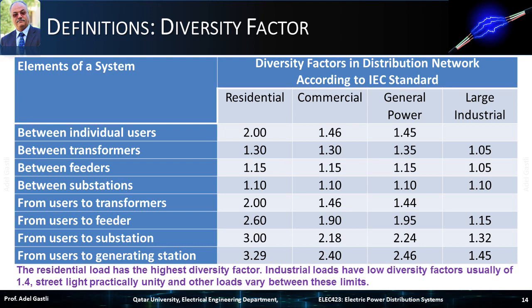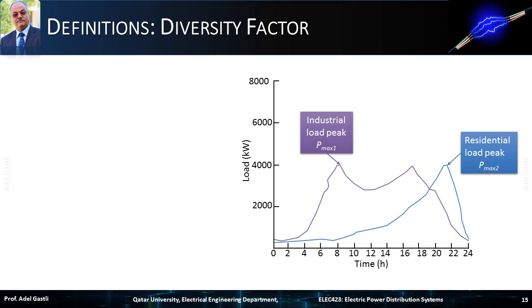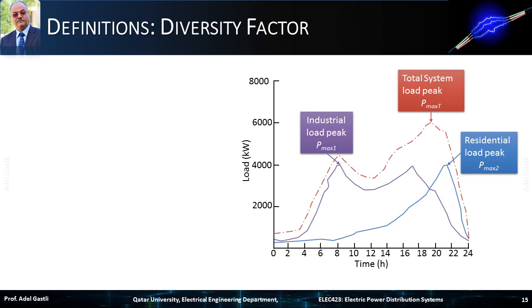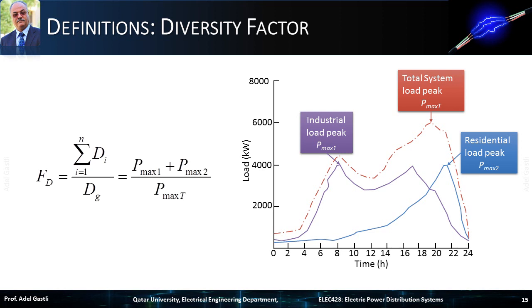Note that the more upstream you go, the higher the diversity factors. The residential load has the highest diversity factor. Industrial loads have low diversity factors, usually around 1.4; street lights are practically unity; and other loads vary between these limits. A graph illustrates different load curves for industrial and residential loads, which exhibit different peak loads at different times. The combined total system peak load seen from the distribution substation exhibits a different shape and peak load, and the diversity factor is calculated as the ratio of the sum of industrial and residential peaks to the total system load peak.